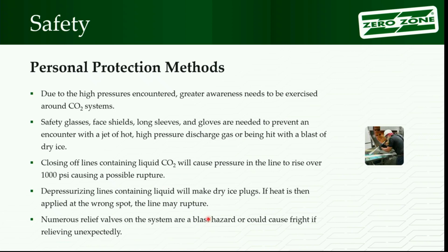Where you're standing, where's your body position as it relates to a safety relief valve? Because if one goes off, you're working on it. If you're working on a system, a lot of times you're probably working on it because something's not right with the system. So if that valve releases, one, where's your face? If they're outdoor units, those safety valves typically aren't piped vertically up high. They might be right on the package at your head height, a little higher than your head. So where's my face, where's my body in relationship to that release valve? And then where's the back of my head? If I get startled and kick back, and I'm inside the rack, do I hit my head on the steelwork behind me? So again, safety valves, you need to know where they're pointed, where they go, what's behind them, and kind of understand how jumpy you are if they release.